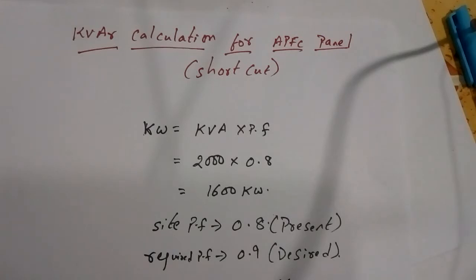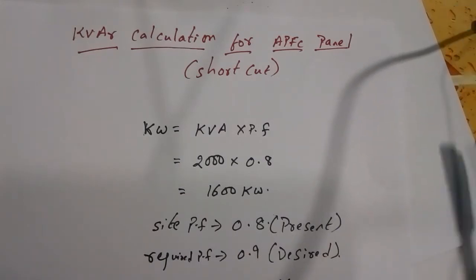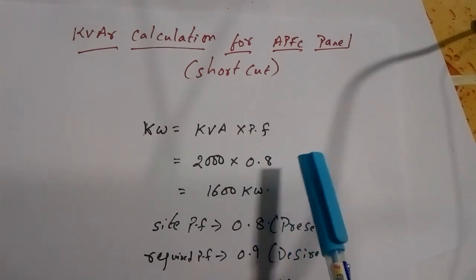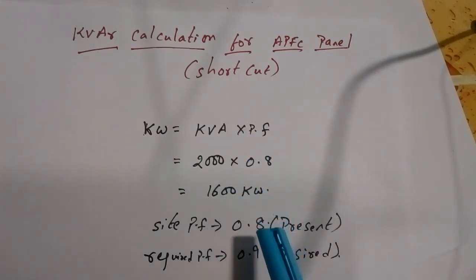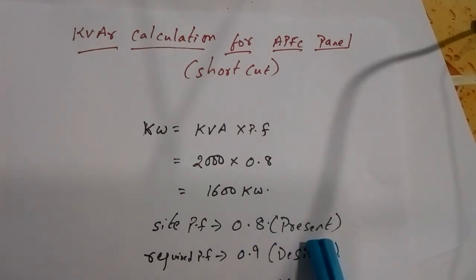In this video I will explain using a conversion factor or multiplication factor. Suppose the transformer installed at site is 2000 kVA and the present power factor of the site is 0.8. So we know that kilowatt equals kVA into power factor: 2000 into 0.8 is 1600 kilowatt. The present power factor at the site before installation of the capacitor bank is 0.8.